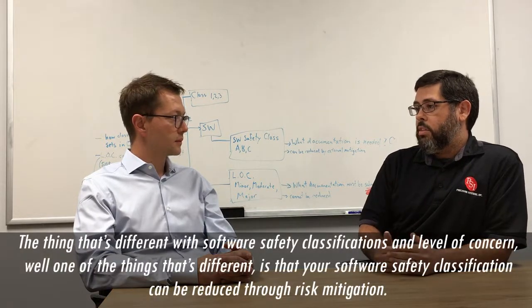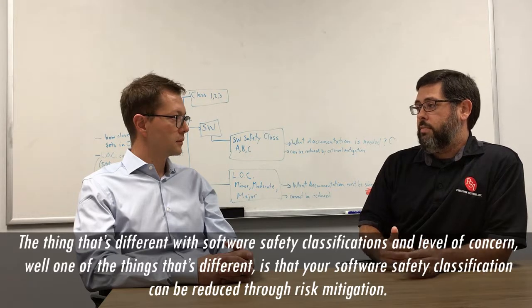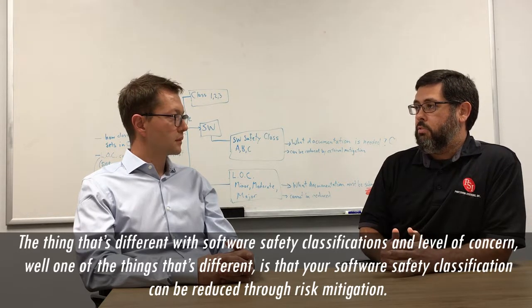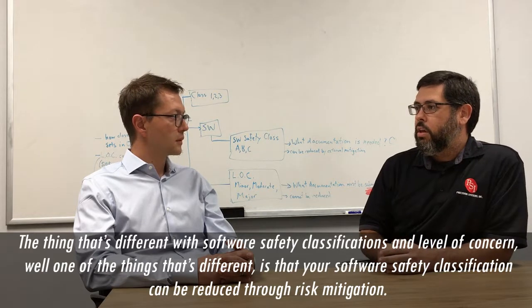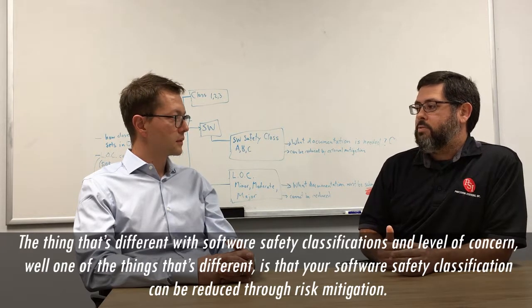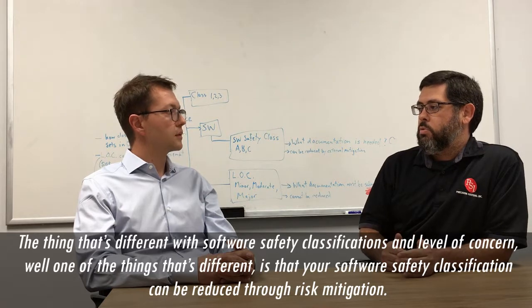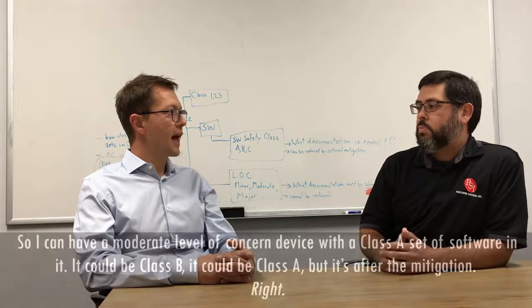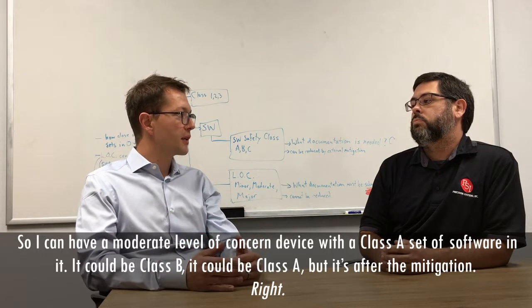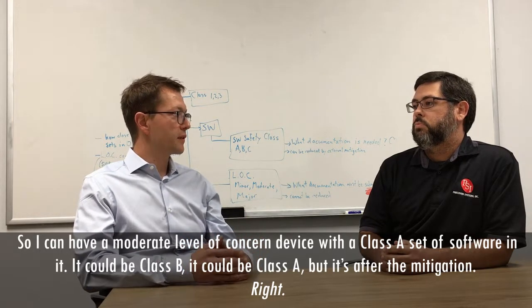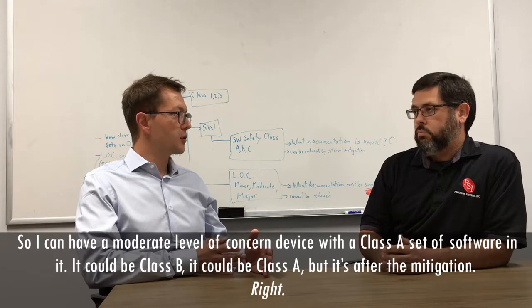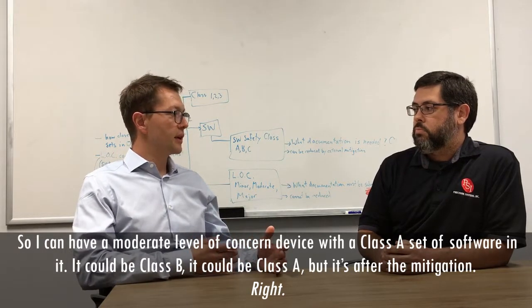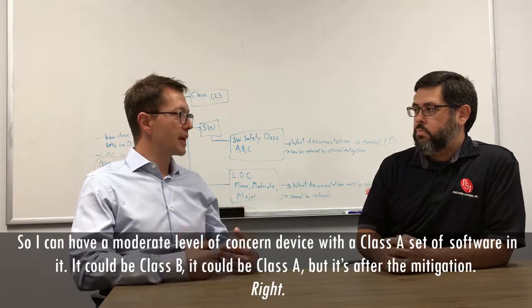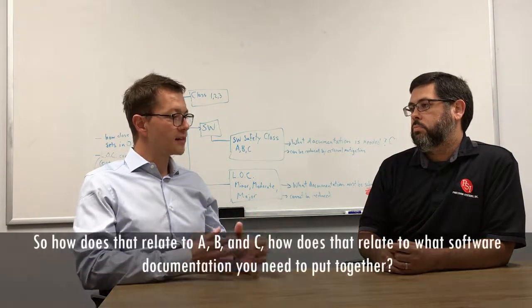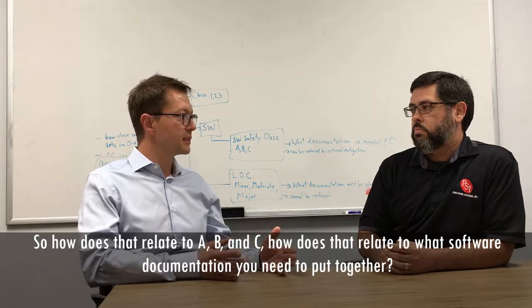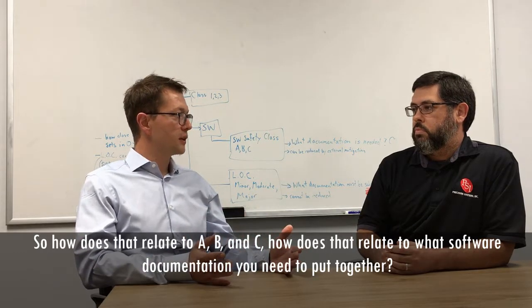Right, and one of the things that's different between software safety classifications and level of concern is that your software safety classification can be reduced through risk mitigation. So I can have a moderate level of concern device with a Class A set of software in it. It could be Class B, it could be Class A, but it is after the mitigation. So how does that relate to what software documentation you need to put together?